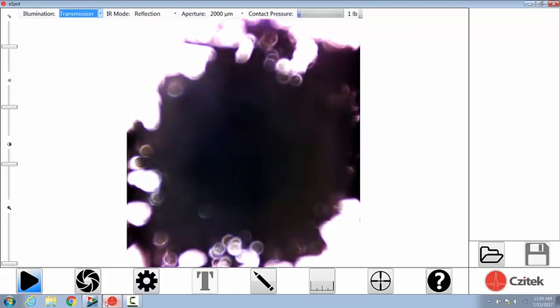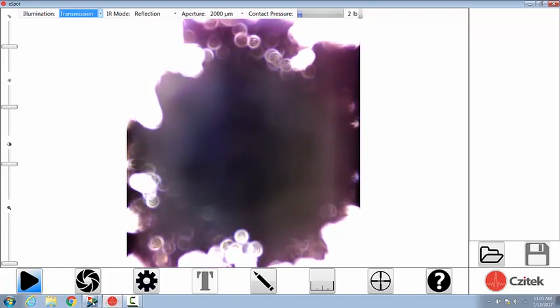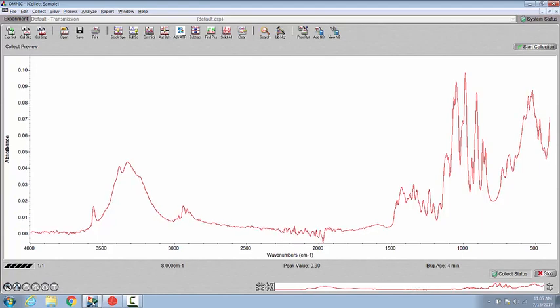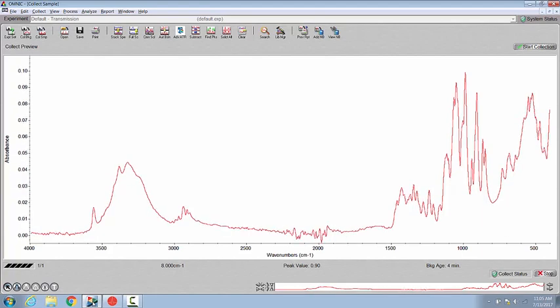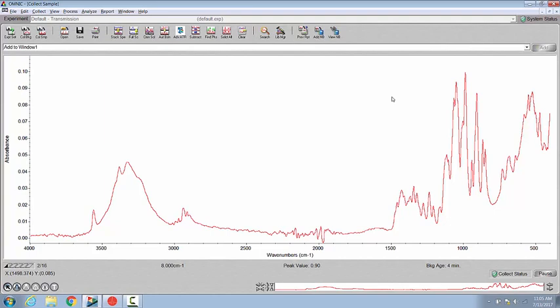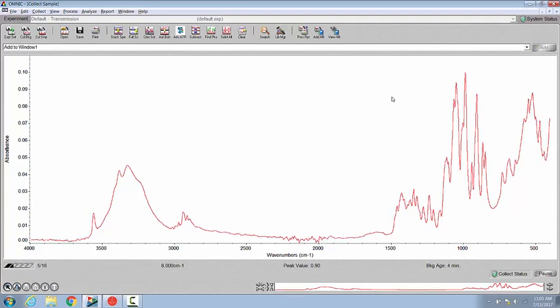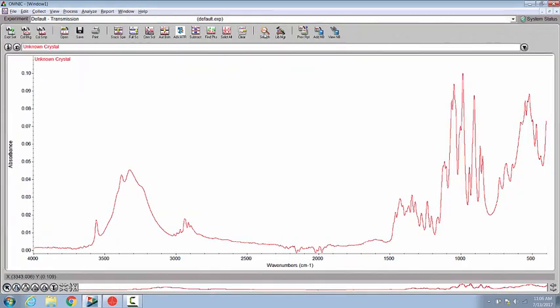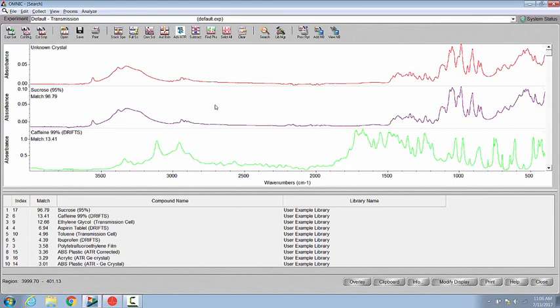We are now bringing the crystal in contact with the surface of the diamond ATR element and observe a wetting of the element with the sample. Weak bands are initially observed in the infrared spectrum. We optimize the contact using a force readout feature within the Surveyor product. We see that the force is increasing, and the band depths increase with contact as spectral quality is maximized. After we collect the data, we search this unknown spectrum against a library of spectra of known materials. The top match from the library is sucrose — common table sugar — with a very high correlation.